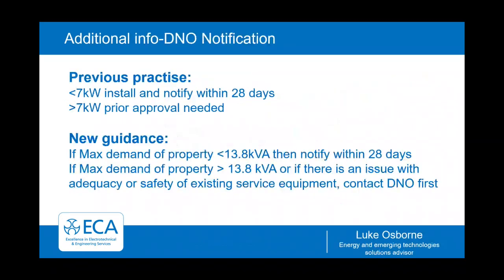Skipped back. The new guidance from the new IET code of practice, which came out recently, says that if the maximum demand of the property is less than 13.8 kVA, so essentially 60 amps, then you can install and then notify the DNO within 28 days. And if the maximum demand of the property is above that, so greater than 13.8 kVA, or if there's an issue with the adequacy or the safety of existing service equipment, you do need to contact the DNO first.